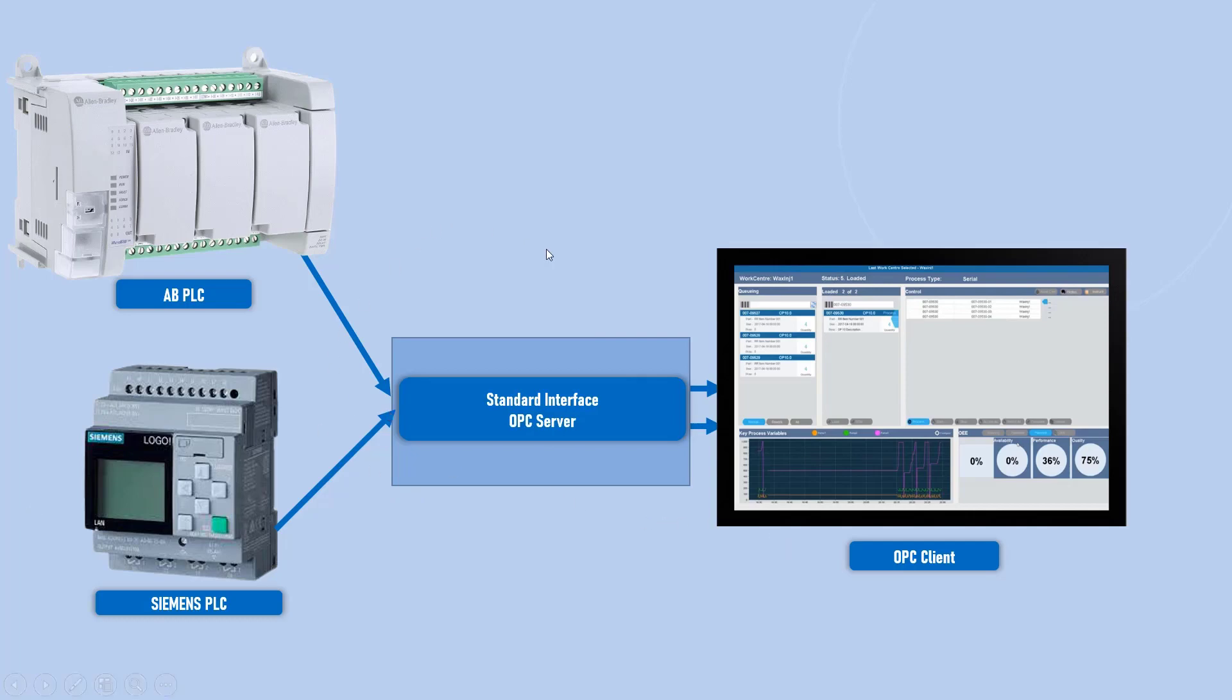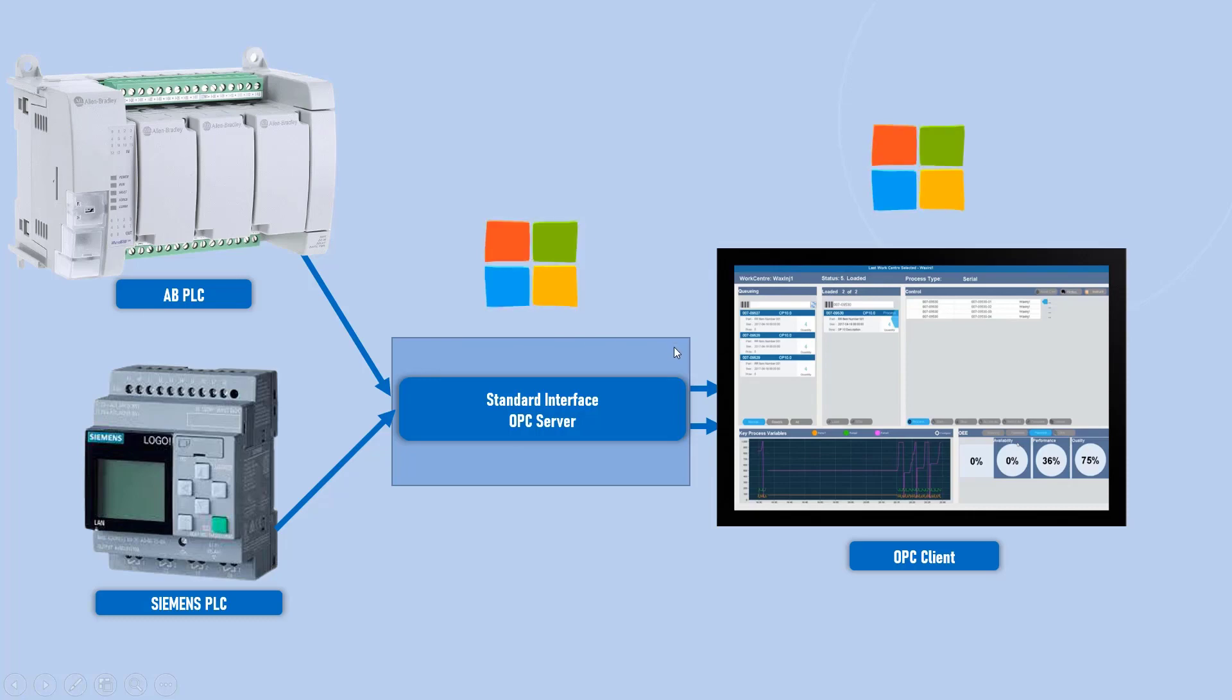So now you got an OPC DA technology, which is one of the very helpful thing, which actually helps you to communicate with different vendors. OPC Classic always uses Windows environment. Your OPC server should have a Windows and your OPC client, which is your HMI, should have a Windows. Otherwise, they can't use OPC Classic.